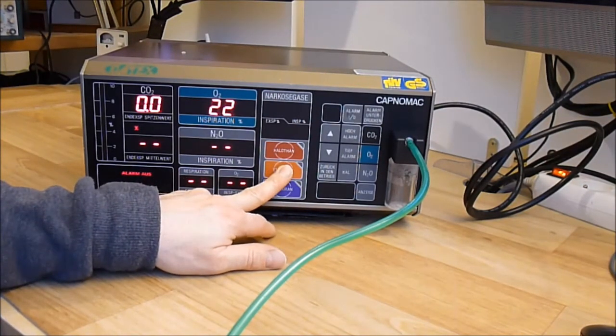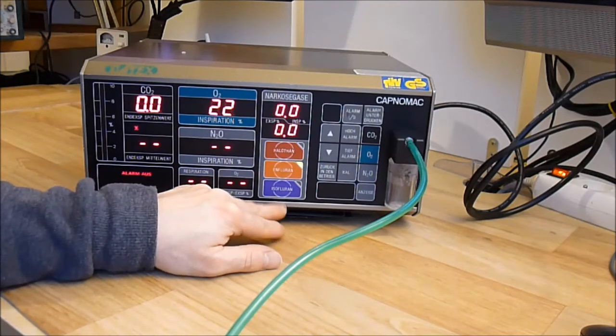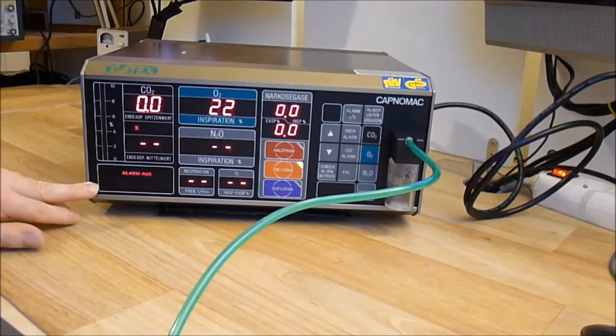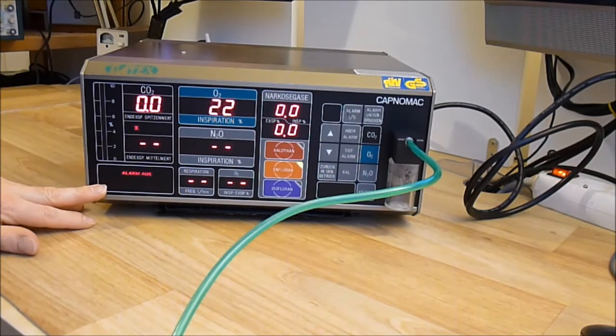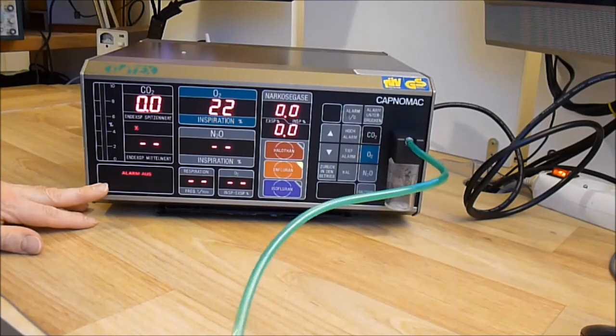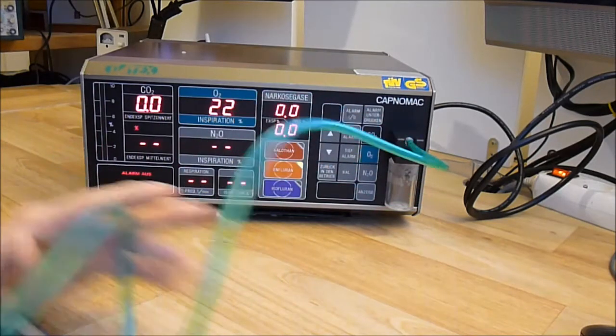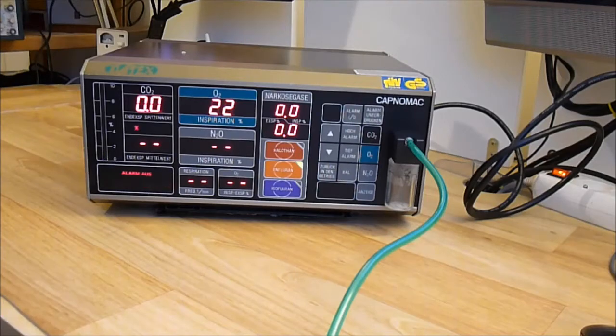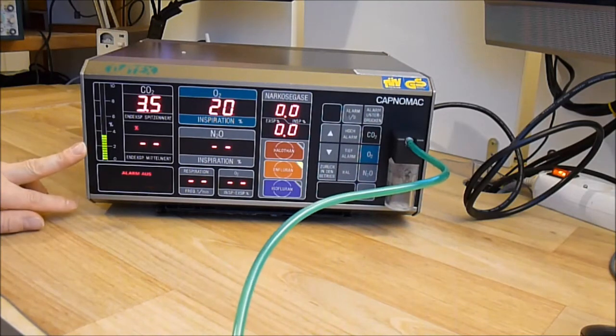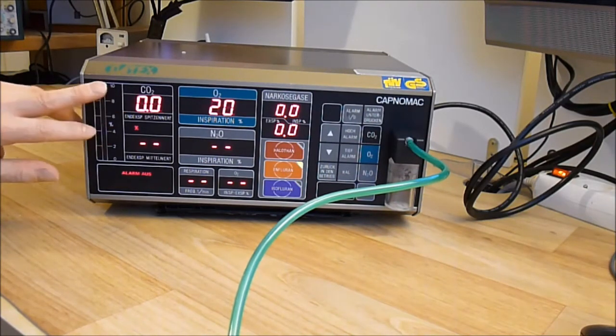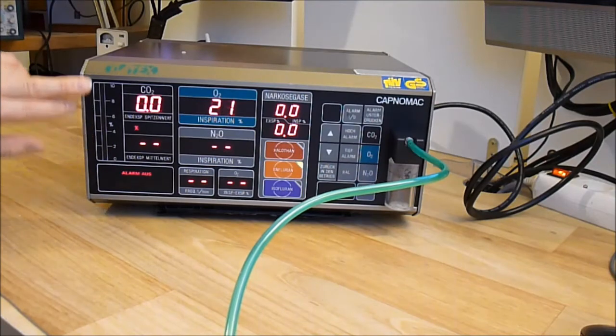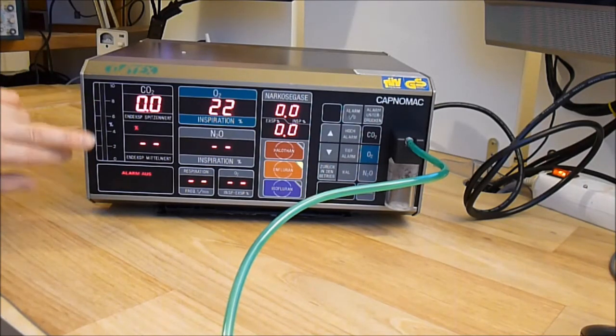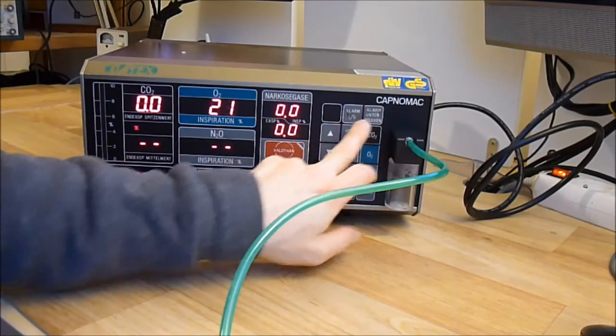I can activate gas measuring. So now, as you can see, it is written it is in apnea because I do not blow in the thing. So as you can see, when I blow, it measures CO2 concentration and this level here does light up.